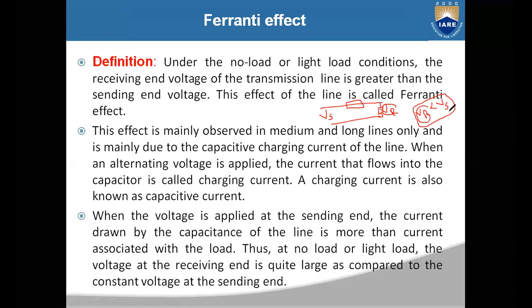The Ferranti effect can be observed only on no load and light load conditions. It can be defined as: under no load or light load conditions, the receiving end voltage of the transmission line is greater than the sending end voltage. This Ferranti effect will mainly be observed in long transmission lines and very rarely in medium transmission lines.